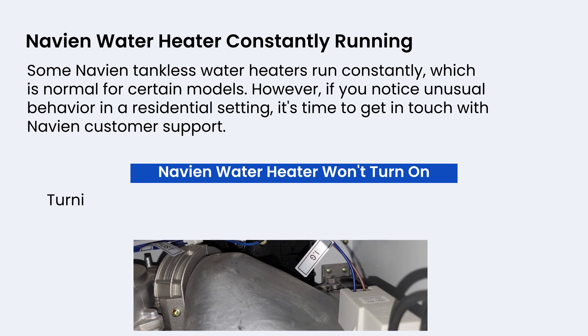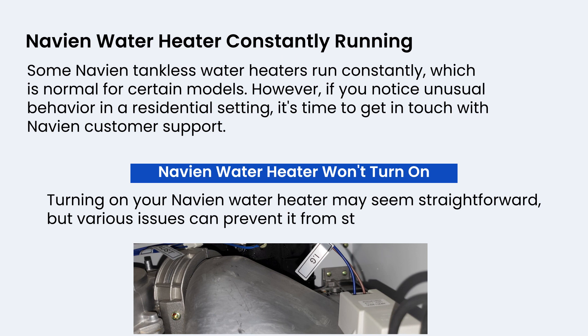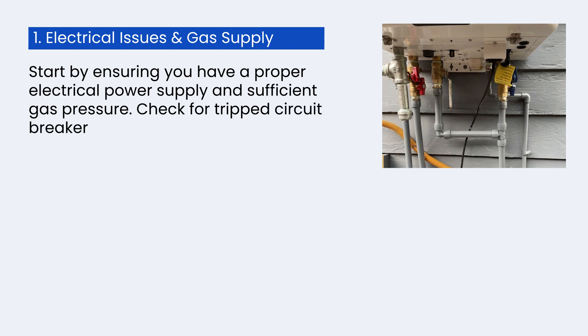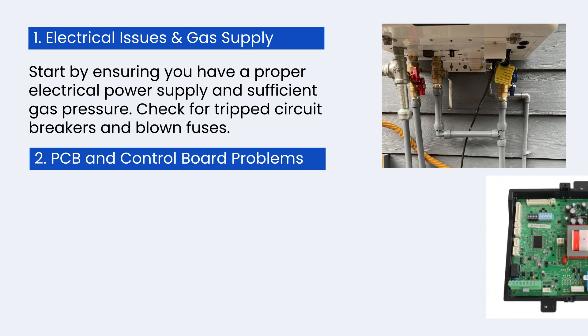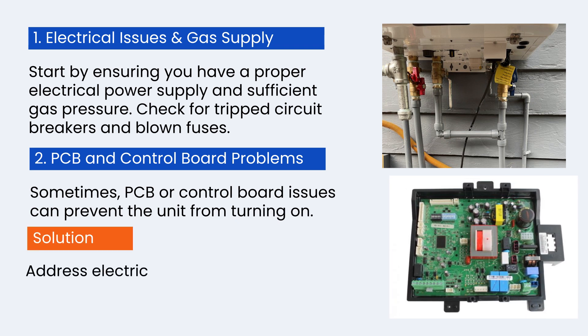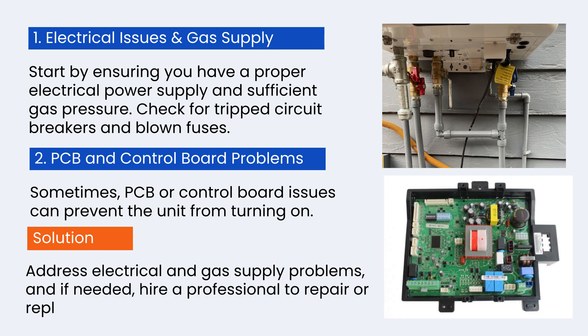Turning on your Navien water heater may seem straightforward, but various issues can prevent it from starting. Start by ensuring you have a proper electrical power supply and sufficient gas pressure — check for tripped circuit breakers and blown fuses. Sometimes PCB or control board issues can prevent the unit from turning on. Address electrical and gas supply problems and if needed, hire a professional to repair or replace the PCB.